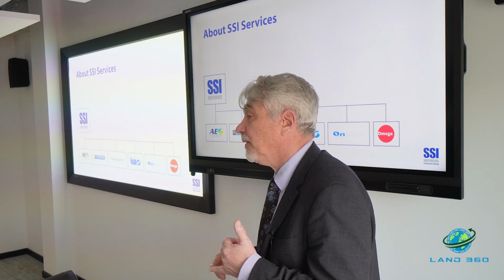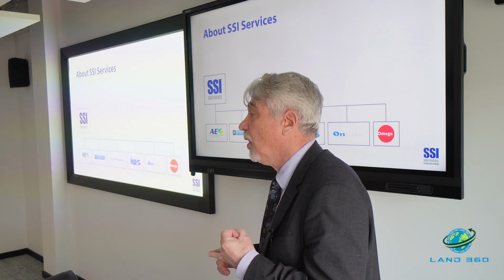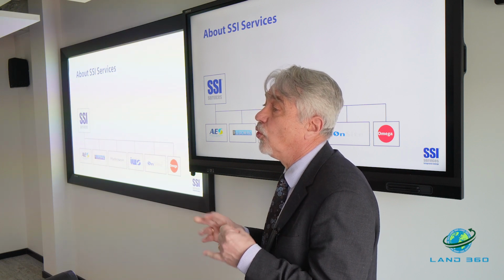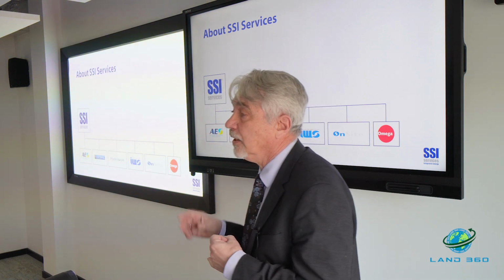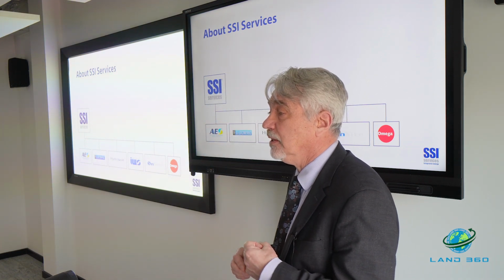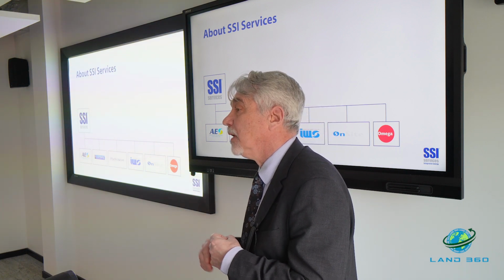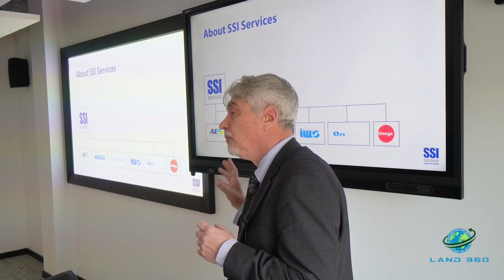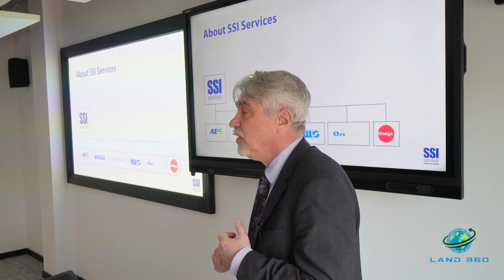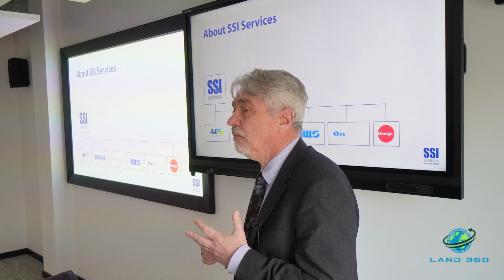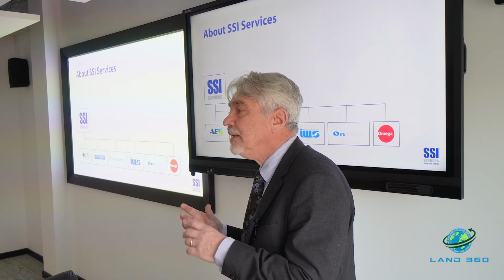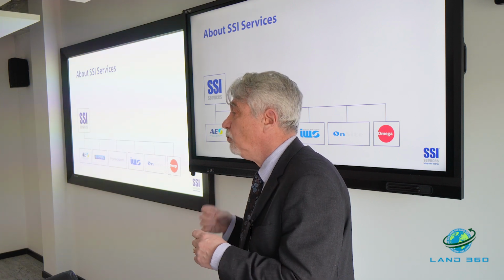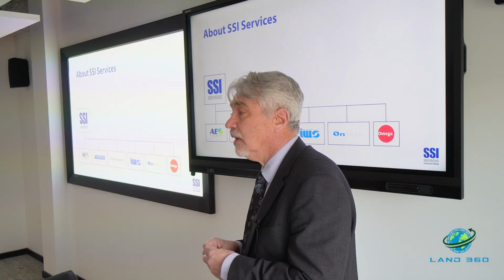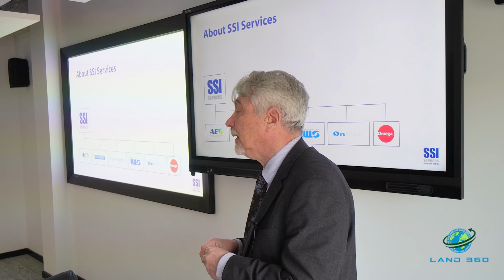Eden have drilled a 5 kilometre borehole to take advantage of the core temperature of the earth, and are utilising that to heat the domes in the Eden - I don't know if any of you have been to the Eden Project, but heating the domes. On-site did the pipe work from the borehole to the energy centre, which is about 3 kilometres of pre-insulated steel pipe with welded joints, then re-insulated. So very good at putting pipe in the ground, very clean.